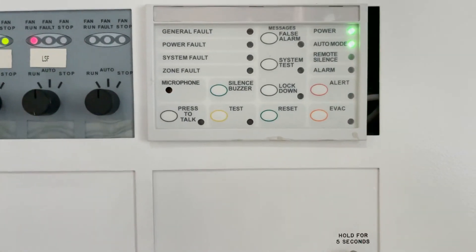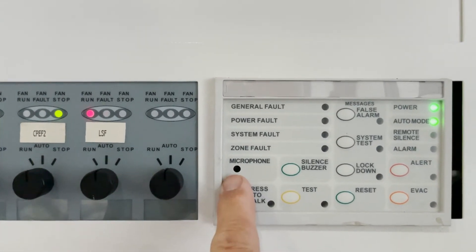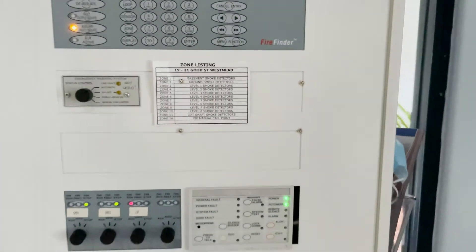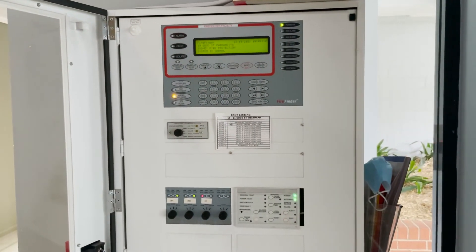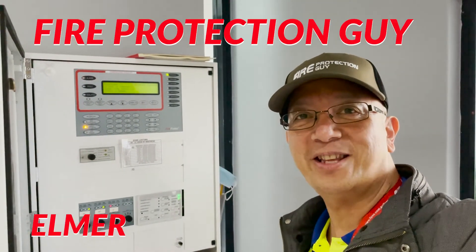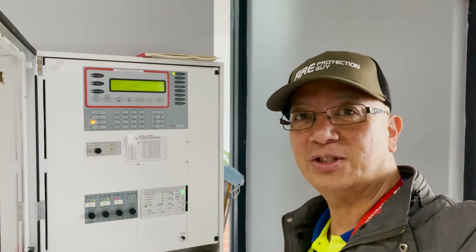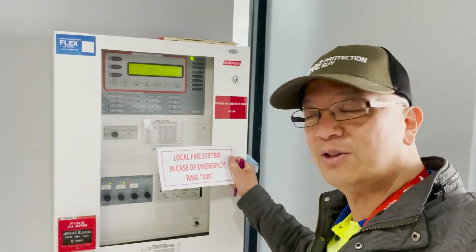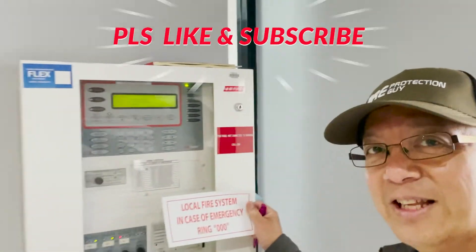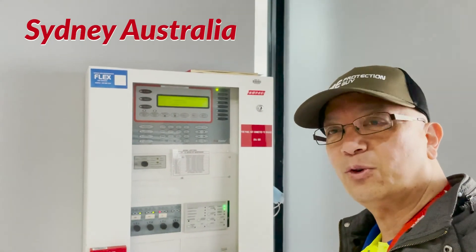So we put everything to normal, and that's normal — all is done. You can also press that button and use the microphone to talk. So that's how we test monthly the fire indicating panel for Ampac FireFinder. Now I have completed my testing, so we fill up the logbook and everything is done. But since this is a local fire alarm system, what I'm going to do now is install a sticker: 'Local fire system — in case of emergency, ring triple zero.' The fire panel is not connected to the fire brigade, so call triple zero. The older sticker is not compliant anymore; this one is compliant. So we're going to put a sticker on there.